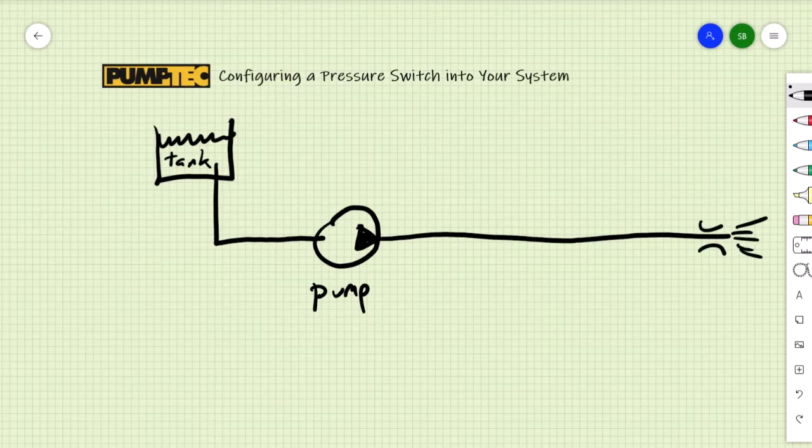The spray nozzle size is very important in a pressure switch system. You have to make sure that when all the flow is going out the spray nozzle, the pressure does not go over the setting on the pressure switch.